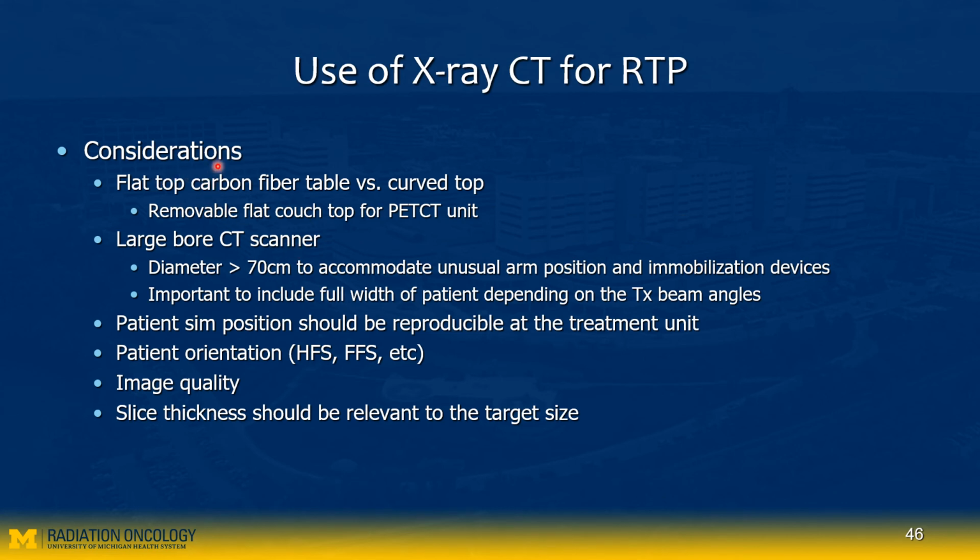So what are some considerations for the radiation oncology CT scanner as compared to the radiology CT scanner? Our CT scanner has a flat top table, not the comfortable curved top the radiology scanners have, because our treatment table is also flat.